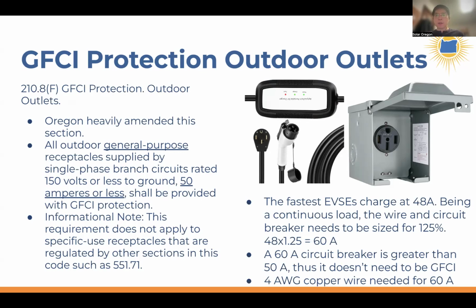The fastest Level 2 chargers use 48 amps, and being a continuous load, you're charging your car for hours. Code requires that wire to be sized for 125% of 48 amps, so that's 60 amps. A 60 amp circuit breaker is larger than 50 amps, so this requirement doesn't actually apply to a 60 amp circuit - that's where GFCI is not required.